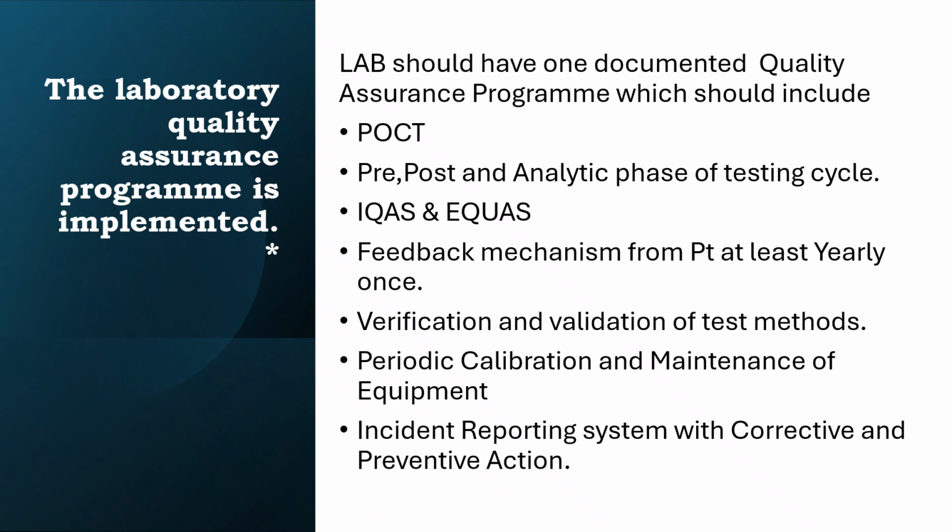Labs should have one documented quality assurance program, which should include the POCT, point of care testing, pre- and post-analytical phases of the testing cycle, IQAS, EQAS, feedback mechanism for patients at least yearly once, verification and validation of test methods, periodic calibration and maintenance of the equipment, and incident reporting with corrective and preventive action. These are the things they can prepare as a quality assurance manual and include all the points in that.